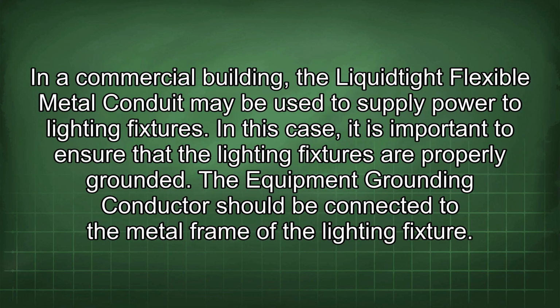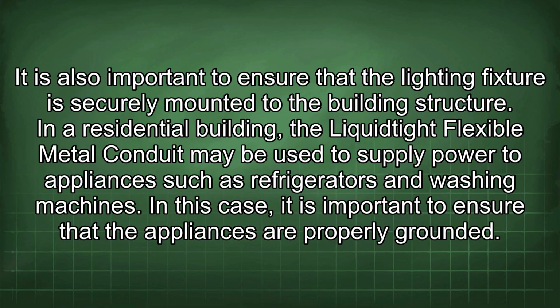In a commercial building, the Liquidtight flexible metal conduit may be used to supply power to lighting fixtures. In this case, it is important to ensure that the lighting fixtures are properly grounded. The equipment grounding conductor should be connected to the metal frame of the lighting fixture. It is also important to ensure that the lighting fixture is securely mounted to the building structure.